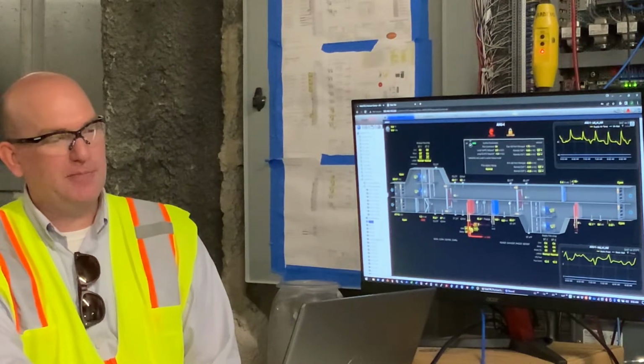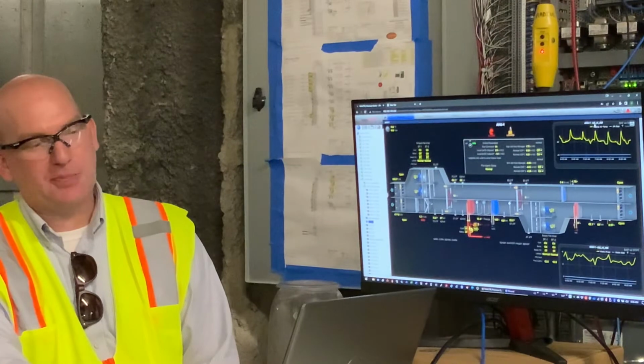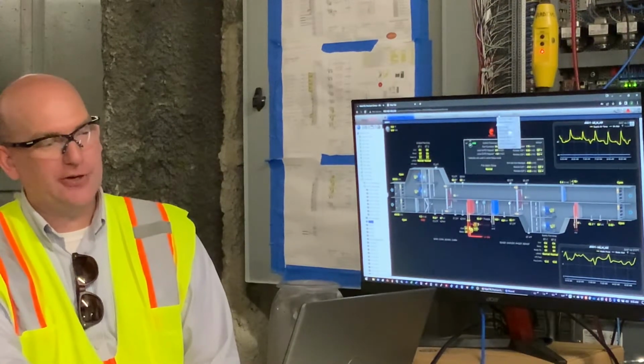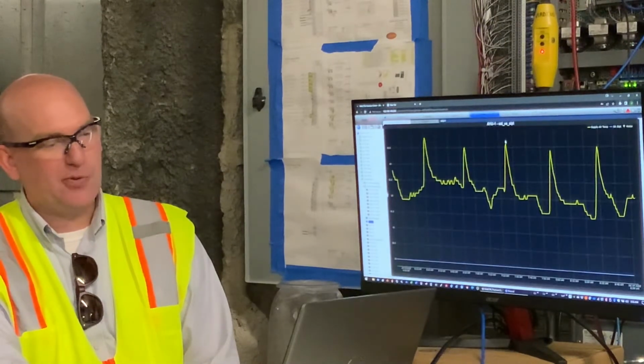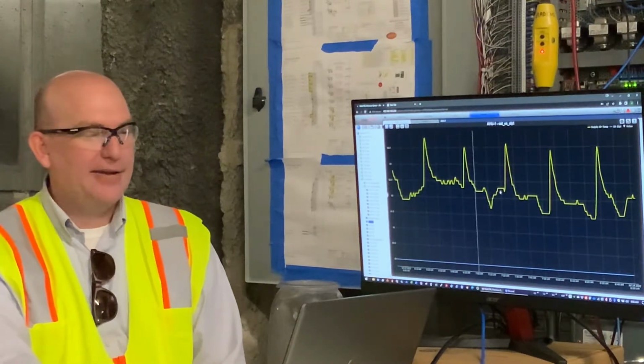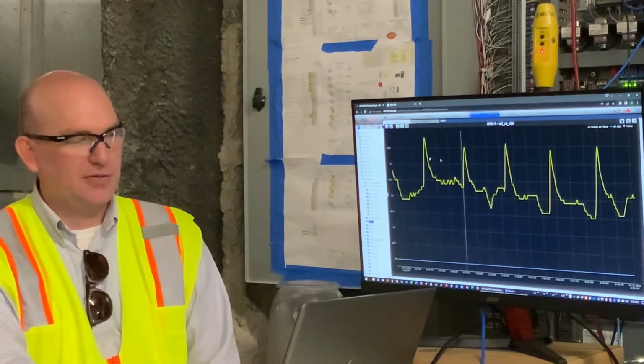So if I go in and we see this particular trend graph at the top, supply air temperature versus set point, custom trends are housed here in this drop down. So if I go over here and I say SAT versus set point, now it takes me into specifically that trend. And it gives me the ability from the trend itself to see all different types of information.